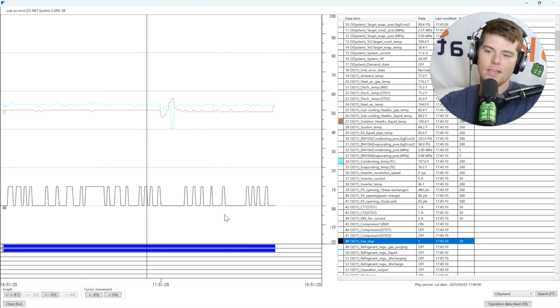If I'm making 5 degrees of subcooling, how fast is the fan running, right? And again, it goes back to the same thing. If I have a unit that's in heating and my superheat across my outdoor coil is just really, really low, is my fan all the way up? Yeah, it is all the way up. Okay, well, then something's restricting the outdoor coil to get airflow across it, right? Or the system's overcharged. But again, I can't just say pinched off pulses, low superheat, fan at full speed.